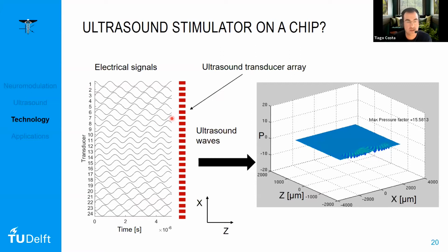So ultrasound waves can be focused electronically by using phased arrays. And phased arrays are a very old technique that was used in radars, and also then adopted by the ultrasound community to make ultrasound imagers. And this is basically, instead of having a single disc of piezoelectric material, we divide it into small elements, and then we drive them with electrical signals that resemble the lens, that have the same kind of curvature of the lens. And you see here that kind of focusing profile in the electrical domain, and what we get in the acoustic domain or in space is the focal spot being created in a specific location in space that matches pretty much the geometrical focal spot of this lens.